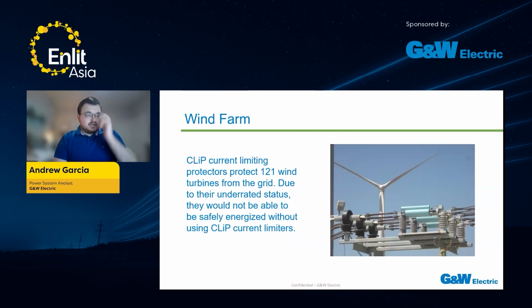Here's another example where CLIP current limiting protectors protected 121 wind turbines from the grid. Because this equipment was underrated and was not easily replaced. Specifically, the equipment that was underrated or overdutied was the equipment installed inside the wind turbines, and you only have a very limited amount of space in there. They would not be able to safely energize at all without using the current limiting protectors. So these devices kept their project on time and kept their facility safe.